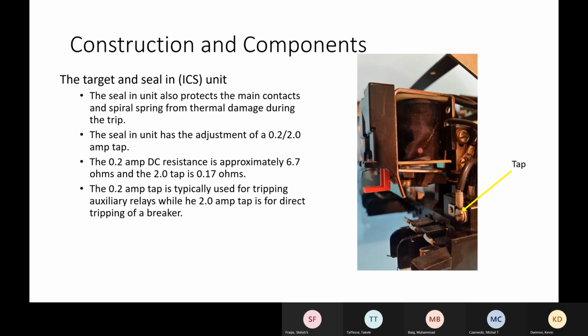And what it does is when the relay operates, a little flag gets dropped. And when you walk up and look at the case, you can see this flag sitting there. It tells you, hey, I had an A to ground, my A relay and my ground relay both are showing flags. So therefore, I know what happened.